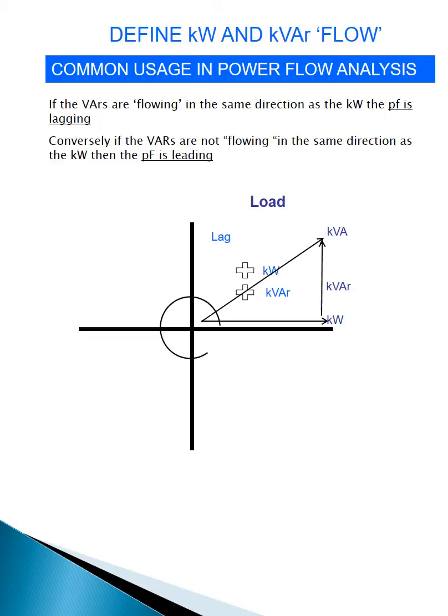Let's look at this in terms of our normal Cartesian coordinate system. The kilowatts, kVAR, and kVA are all positive in the top right-hand quadrant, as this is just the same representation of the current and voltage for a lagging load as we showed previously. kVAR is negative when the load is leading, i.e. the bottom right quadrant. This allows us to assign directions to our vectors for a load. We can also use this idea for generation, because when the kilowatts is flowing out of an entity, then the entity is a generator. The vectors for leading and lagging generator are shown as the top and bottom left-hand side quadrants.